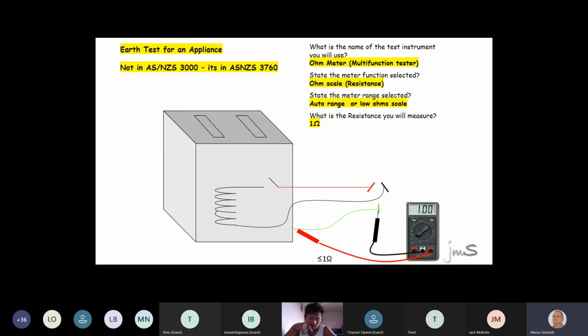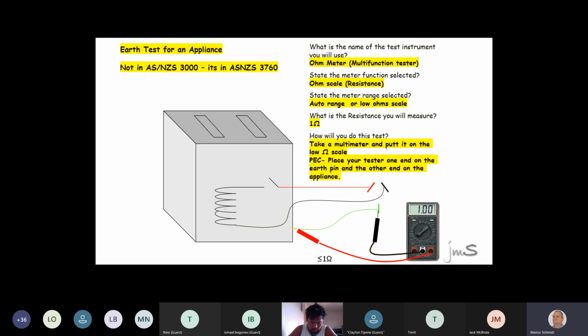Cool. Now this is not in the 3000 book. This is in a standard called AS/NZS 3760. How do you do the test? You're going from the plug to the end of any metal piece. Please do not go and scratch mommy's toaster and say, now I've got a good earth. Normally go to the bottom, there's a screw somewhere, measure to the screw. All right? 1 ohm or less. You can put it on here. Cool. Thank you. So you guys happy with that?